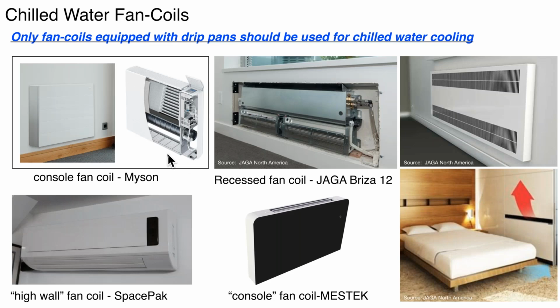Now, multi-zone. We can also distribute chilled fluid, whether it's water or a mixture of water and antifreeze, to several different types of zoned heat or cooling terminal units. Myson makes some fan coils. They do have drip pans in them, and they have the tangential blowers. This is actually the unit I have in my office. It looks like a ductless mini split, and it operates exactly the same way with a remote control. You see there are louvers down here that will open when it's operating. The only difference is this has a hydronic coil rather than a refrigerant coil. Jaga also makes some nice units that can be either recess mounted or surface mounted. Mestek has some fan coil units. So they're available out there.